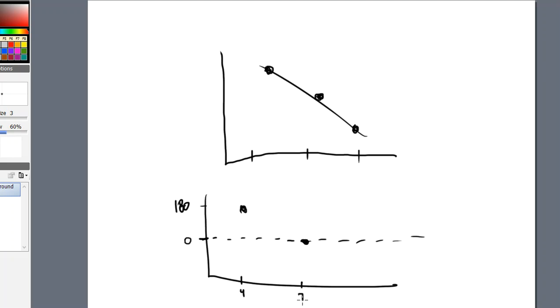So this is pH of 7. And then negative 180 is going to be a pH of 10. So here, let me put 10 out here. So these are my 3 buffers. This is what should happen when I begin to calibrate the probe, and to make sure the probe is reading and functioning the proper way. That's the whole purpose of calibration.